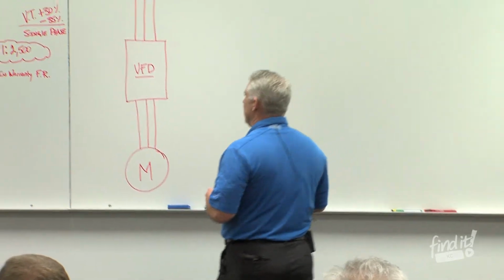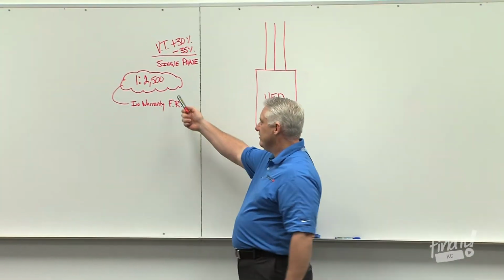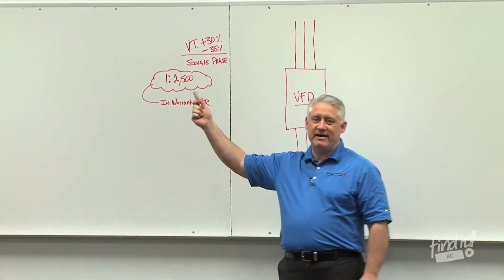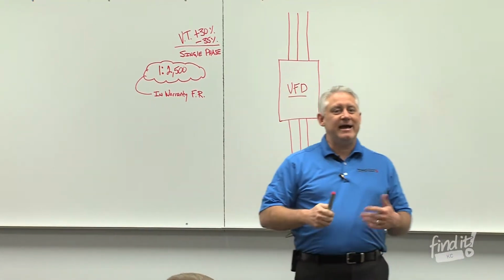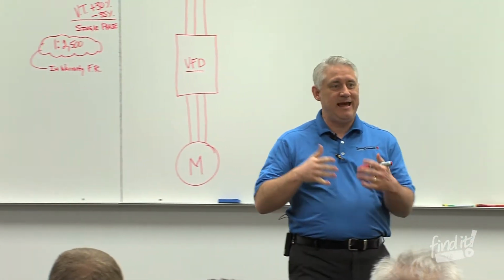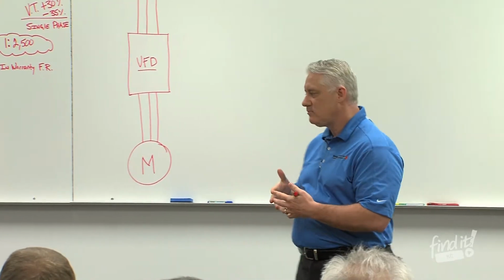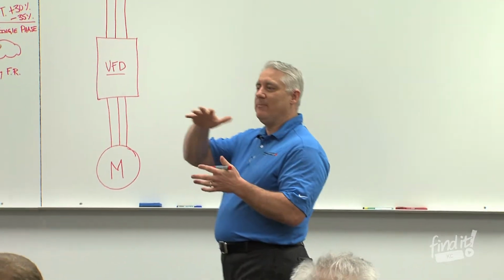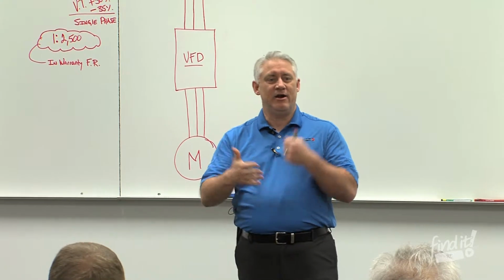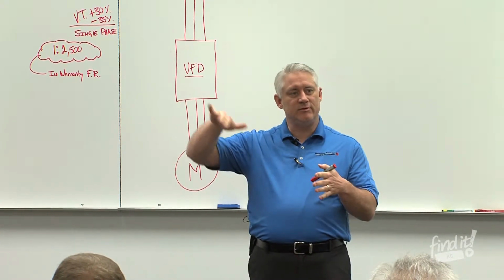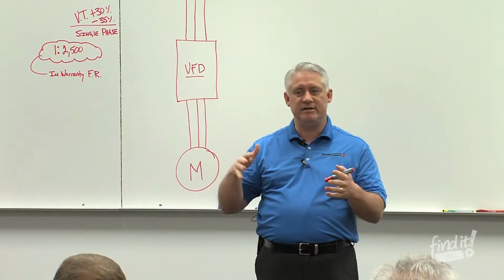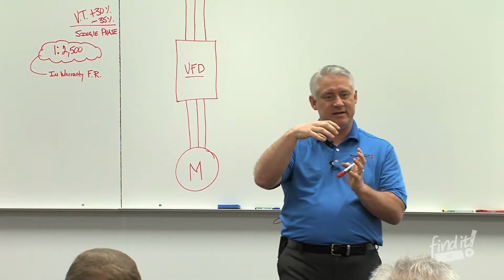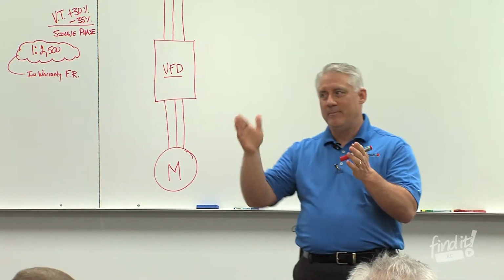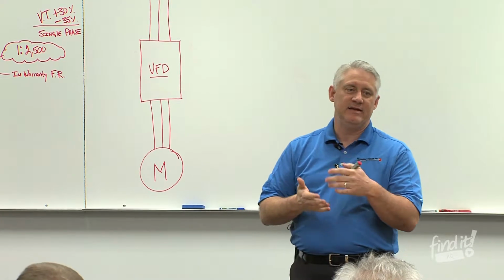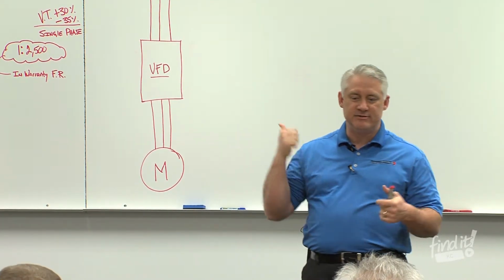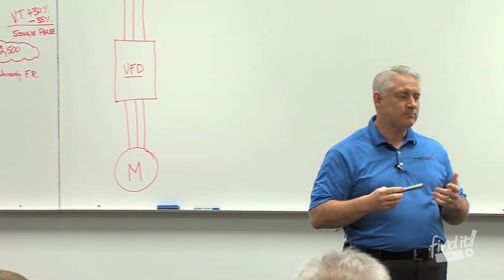Today, most drive manufacturers are seeing an in-warranty failure rate of about 1 in 2,500. So the reason we added bypasses in the 80s was because of that high failure rate, we needed to have the ability to route power around the VFD. With the drive, you get a nice smooth acceleration and we're saving energy. But if something were to happen to that energy savings device, we needed to be able to route power around the VFD. And that's what the bypass is for. We put some contactors in there, and I'll talk about that a little bit more in a minute.